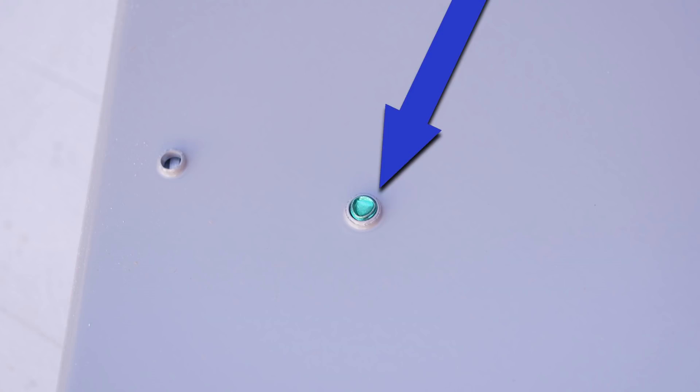An important point: if you're going to be placing this box on a solid surface, this screw needs to be torqued prior to installation of the box because it does stick out from the bottom of the enclosure and that can affect your torquing. You can think that it's torqued all the way, but it's just hitting on a solid surface.